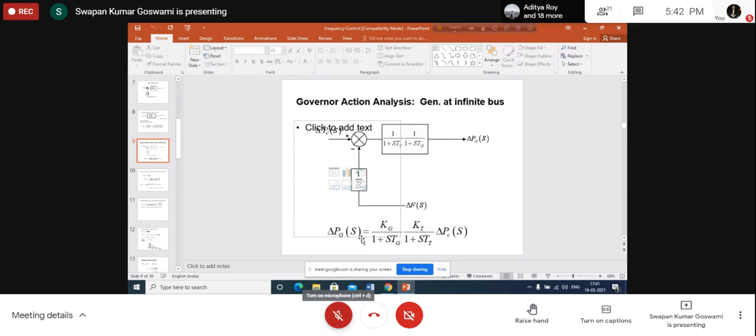Am I clear? And this operation, you know, because you have studied boilers and turbines, either you have studied or you are studying now, is called the throttling operation, throttling of the speed governing system. That means you are not changing the opening of the steam valve by giving some external input, but because of the change in the loading of the generator, the speed at the terminal of the generator is changing. Because of the changing speed of the generator, the governor valve opening is being changed, and this changes by the throttling operation. The governor, it is so called.